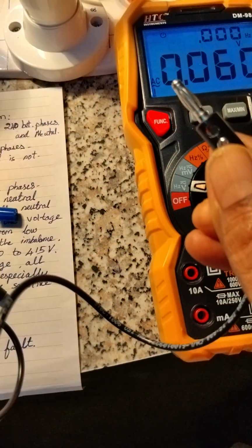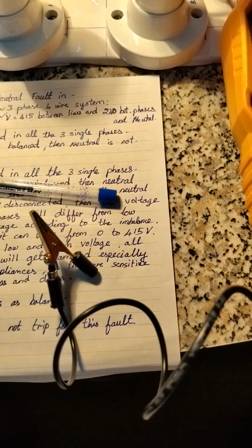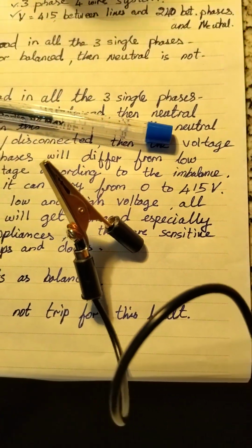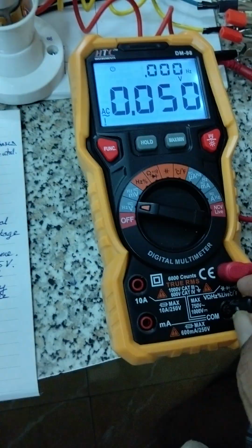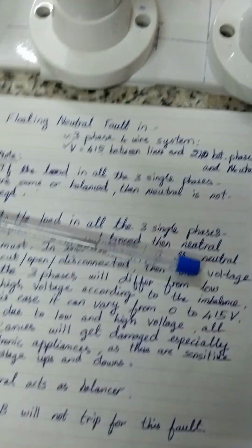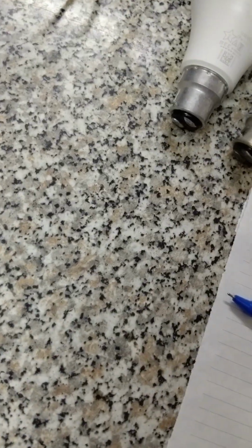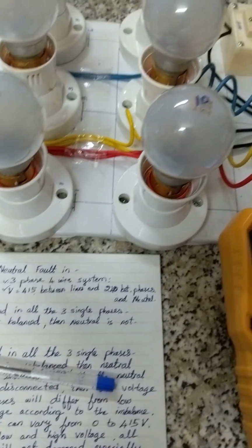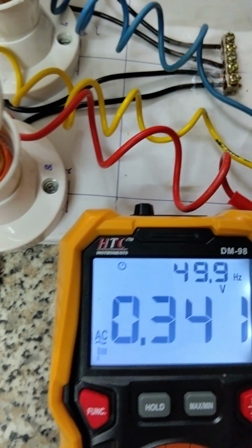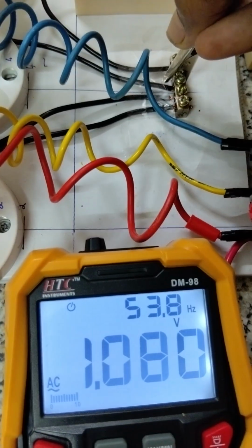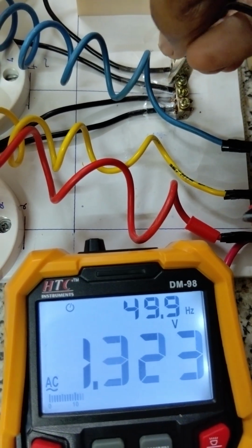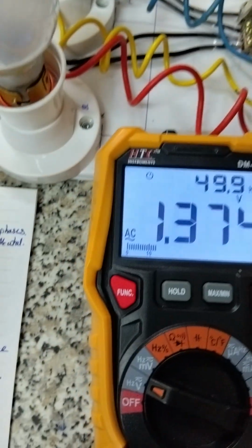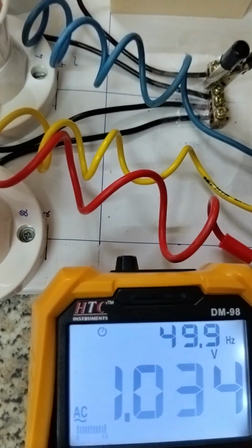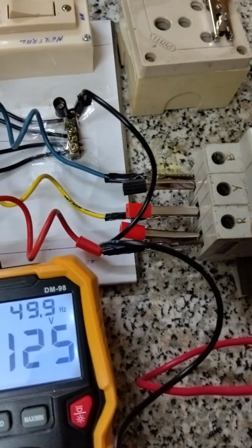And I am attaching a probe with banana at one end and crocodile clip at the other end, just for convenience. So you have to be careful. Check whether it is in off condition, and now I am clamping it to the common link, neutral link or star point. Now I will switch on the three phases.